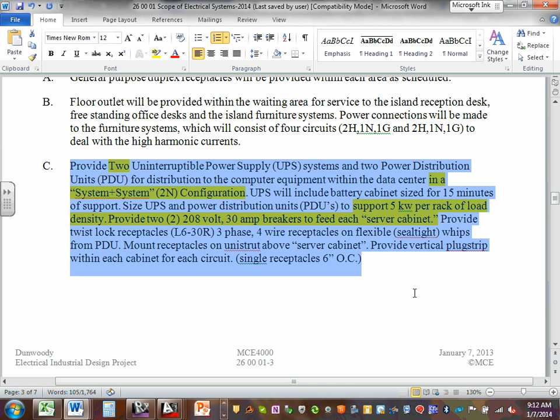When you lose power, the batteries feed that DC middle part, which feeds through the inverter and out to feed the load with AC. So if you lose power, you've got 15 minutes of clean, good power until the batteries die, and then your stuff downstream goes off.